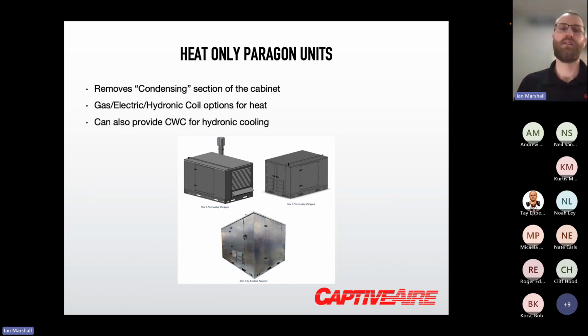We have a newer option called our heat only option. It entirely removes all the DX cooling components from the unit. So it's still our unit, and you still get all the same benefits of the higher end components and construction, just without the DX cooling portion. Essentially the unit becomes an air handler in a way, and we can utilize any of the heat options: gas, electric, or hot water coils. We also now have the option to do a chilled water coil in this unit paired with any of those as well. It could be a good option for buildings that have chilled water loops or hot water loops, and it is available now fully.